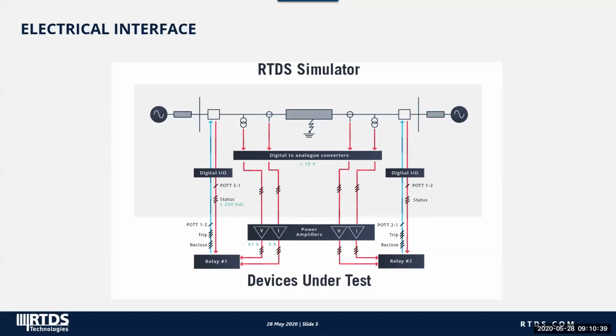If the devices do not support IEC 61850 or it is not required for the specific application, the conventional I/O cards of RTDS will be used for data transmission. The analog output card will be used to send the secondary side voltages and currents of the corresponding breaker from the simulation to, in most cases, the external amplifiers, then to the physical input contacts of the relays. Digital I/O cards will be used to send the breaker status to the relays and at the same time receive control signals, such as trip and reclose signals, sent from the relays back to RTDS to operate the breakers in simulation.